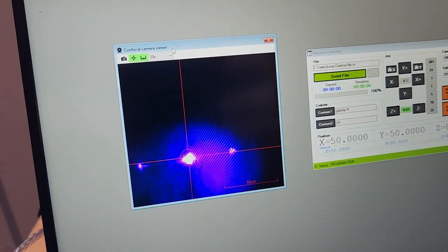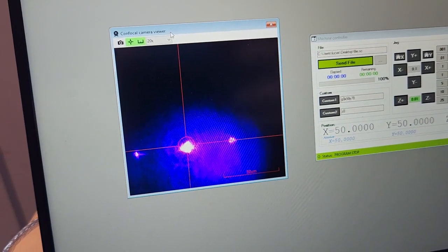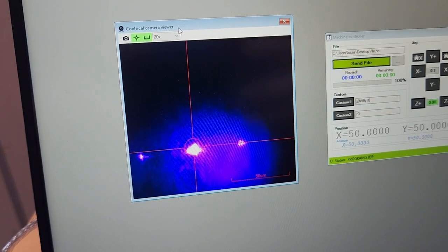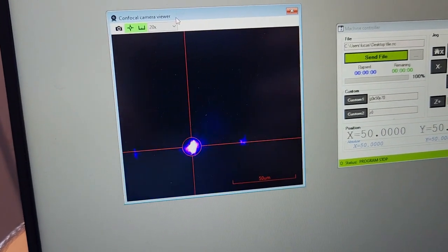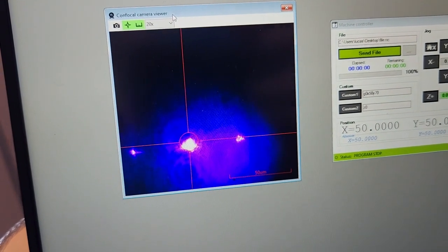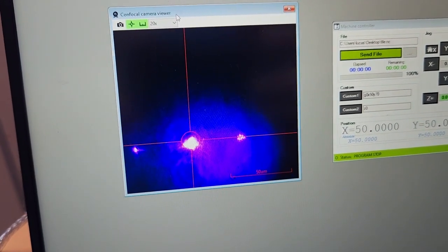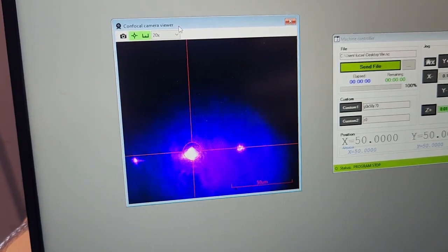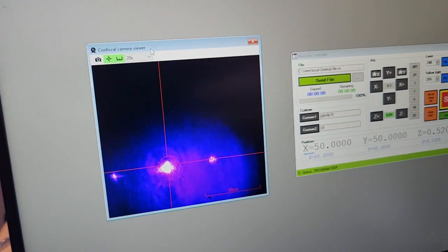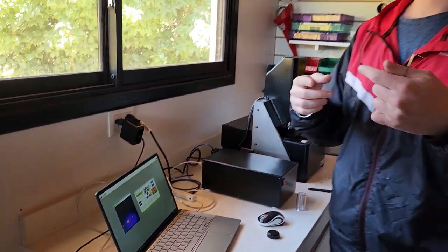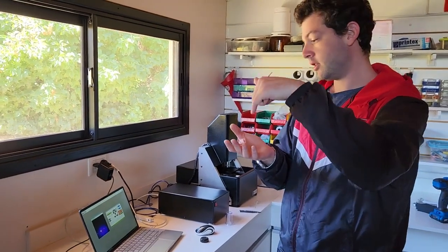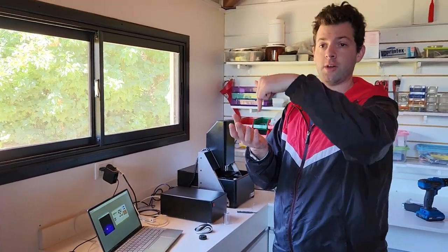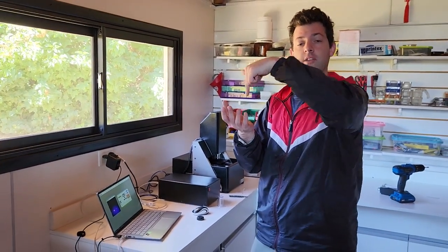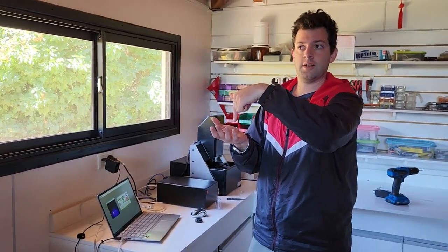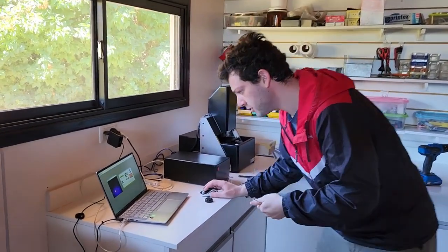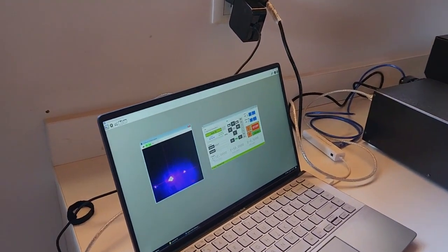Check. See how now it's much brighter. We were clearly not in the middle. What we want is maximum brightness, okay? So we move it in one direction and we see, okay, this is the maximum brightness. In the other direction, okay, this is maximum brightness. You might need to play a bit with both axes, because if you are way out of focus or out of alignment in both directions, when you move one axis you won't have any image in the other. So now it looks like you have maximum brightness.